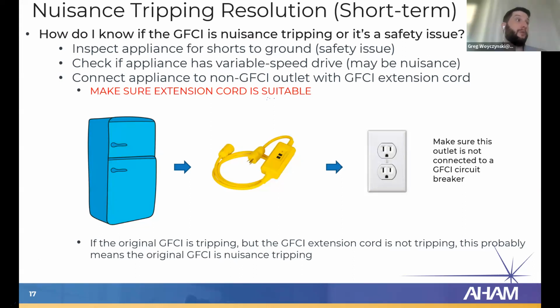Great point, Michael. So you're right, the GFCI extension cord could also be faulty, right? It could also be tripping at these very low levels of safe electrical signals. So the only way this process really helps you is if the breaker is tripping, but this is not tripping, right? That means one of them is more sensitive than the other. They both meet UL requirements. So Michael, that's a great point. Just because your extension cord is tripping, it could still be nuisance tripping. Your refrigerator could still be safe. Okay, so appreciate that clarification.